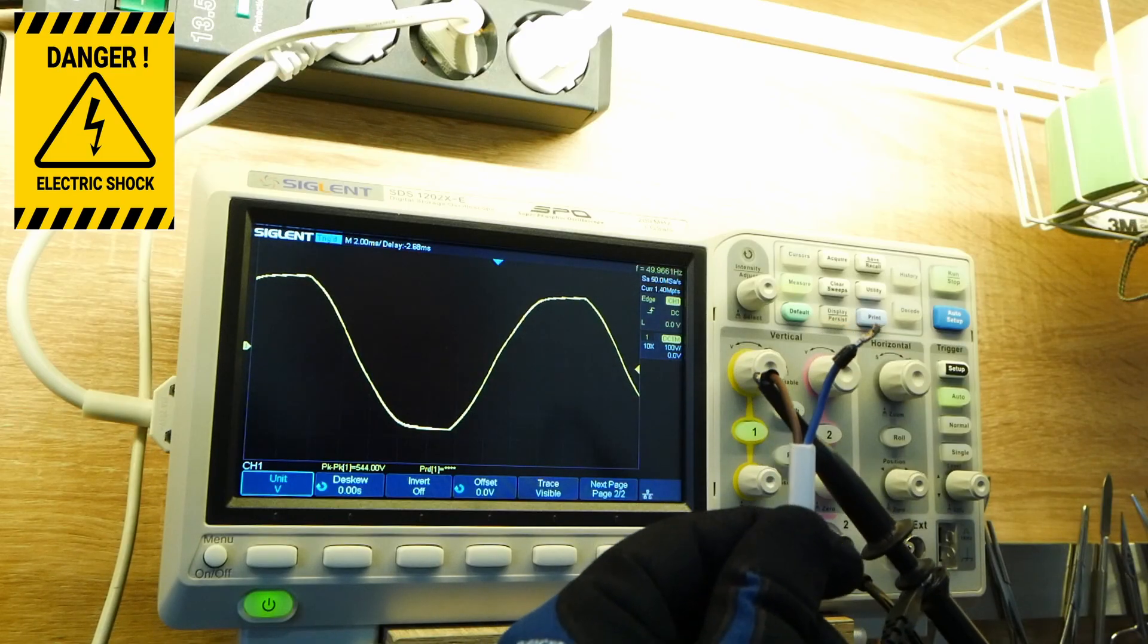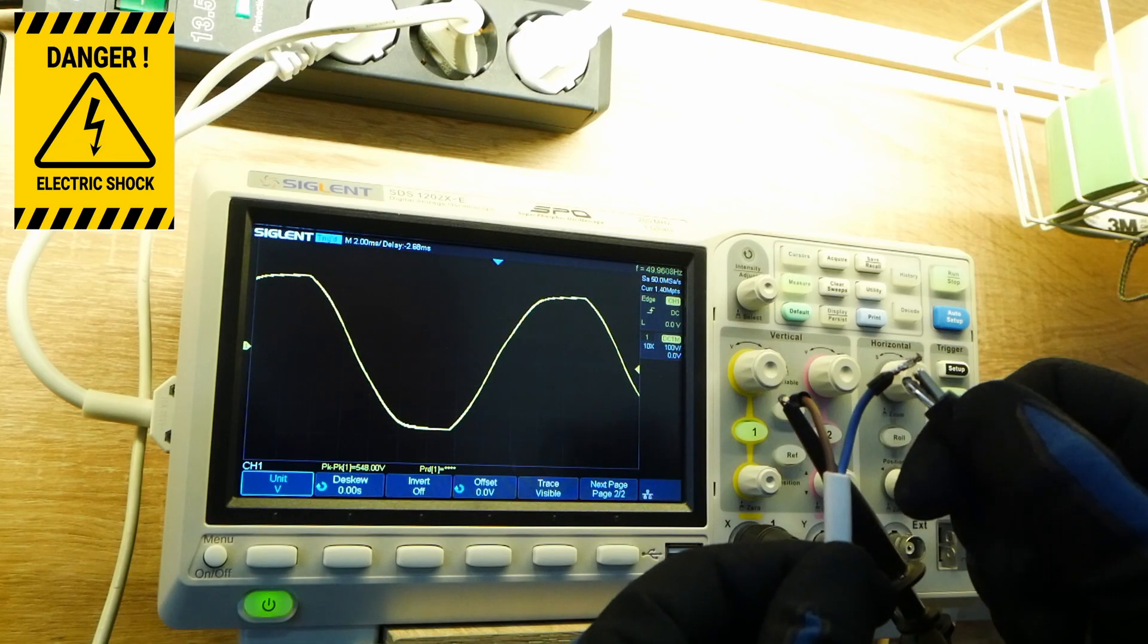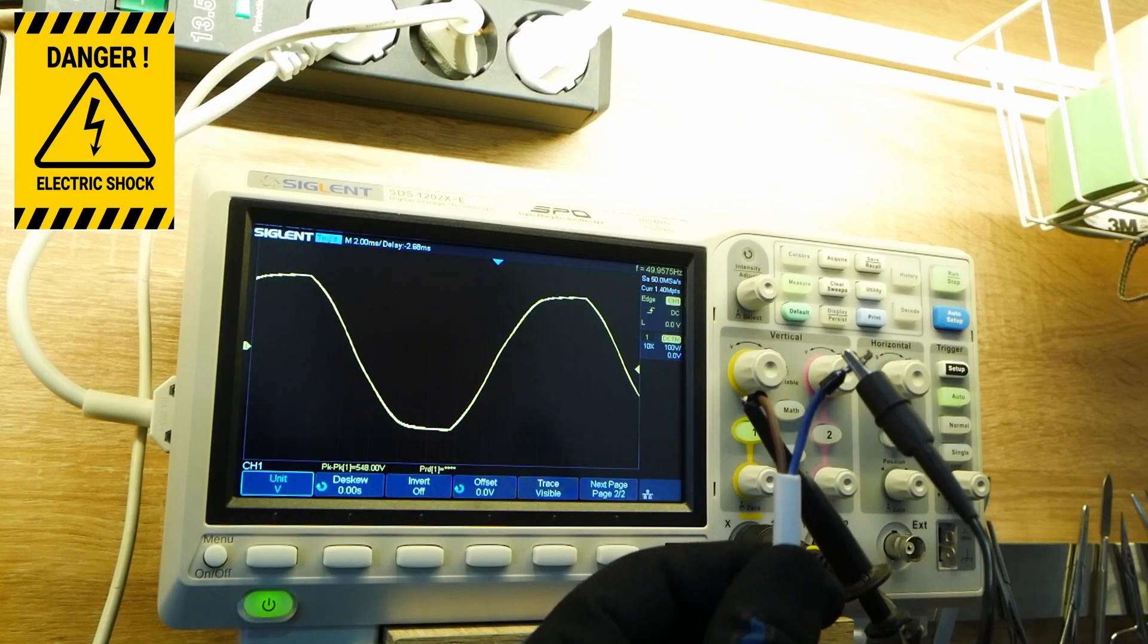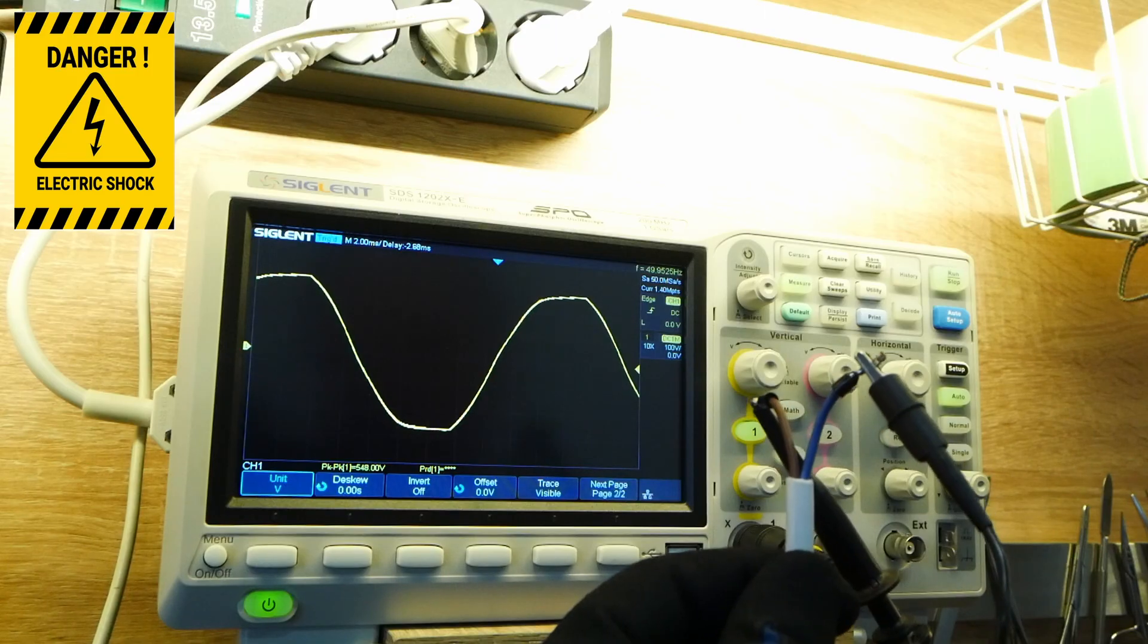So I don't even have to connect my crocodile wire on neutral, I will have a result immediately. And if I connect my crocodile wire on the ground wire, nothing will change because it's already connected in the electrical cabinet—neutral and ground connected to the same point.